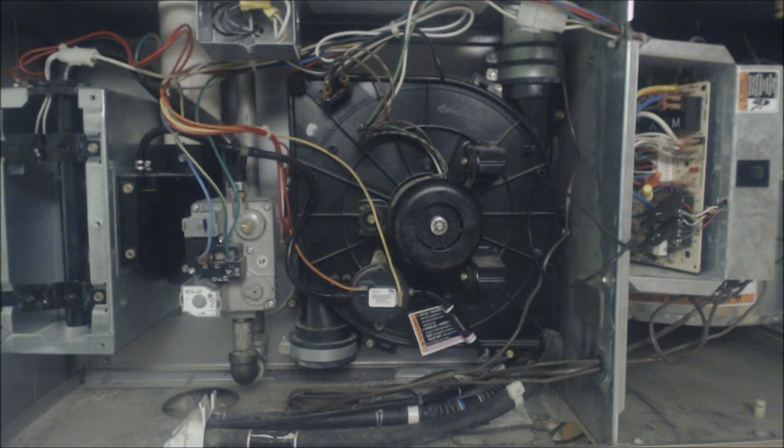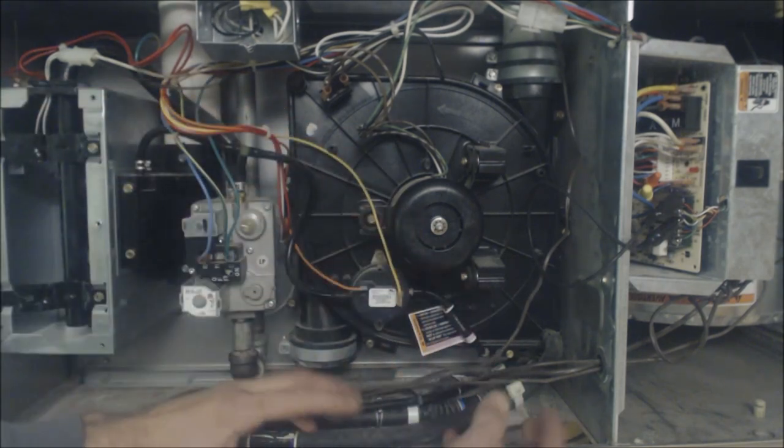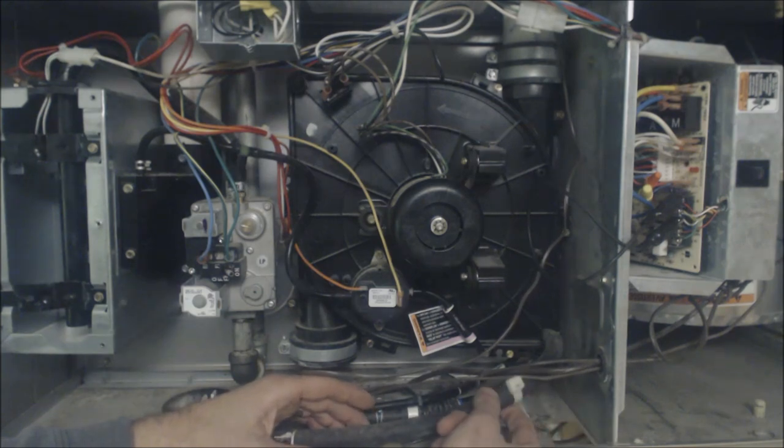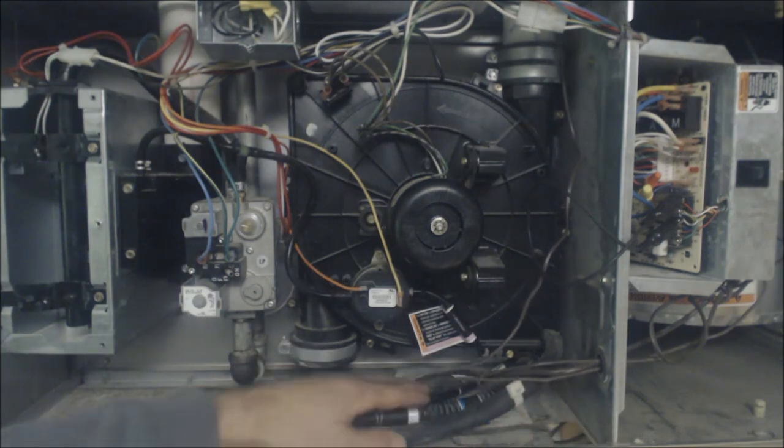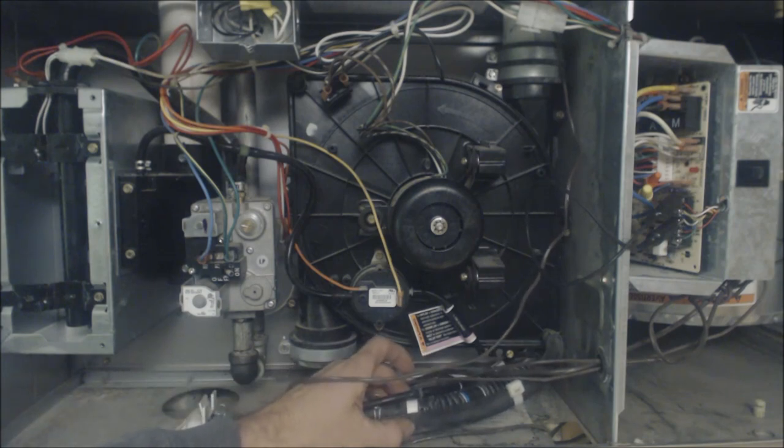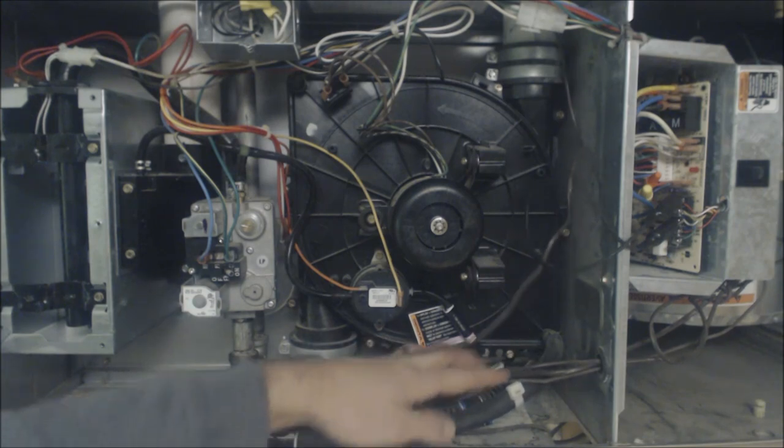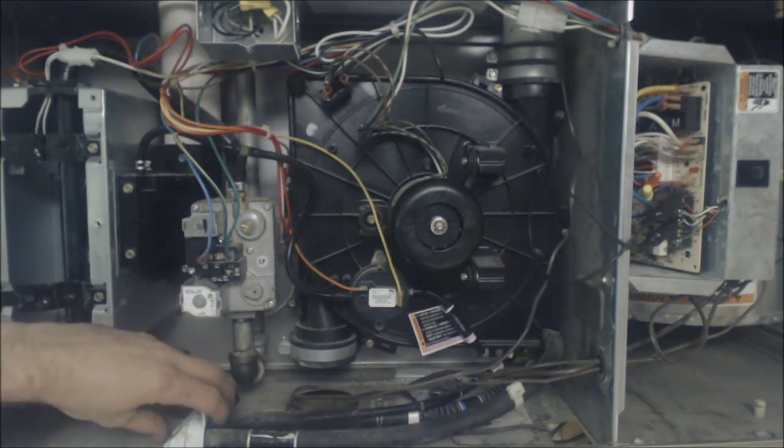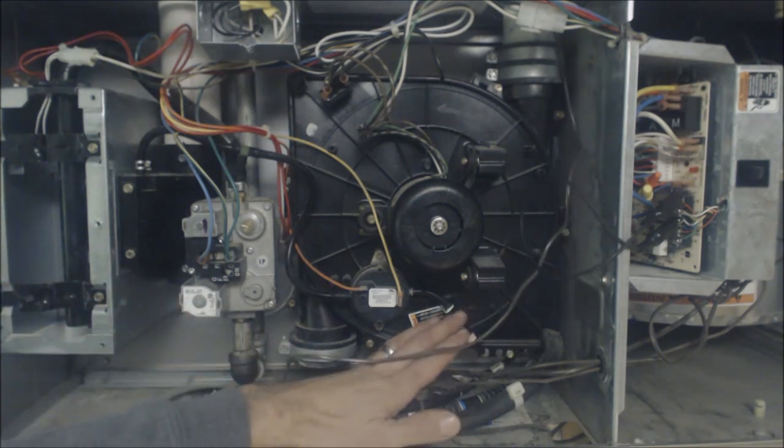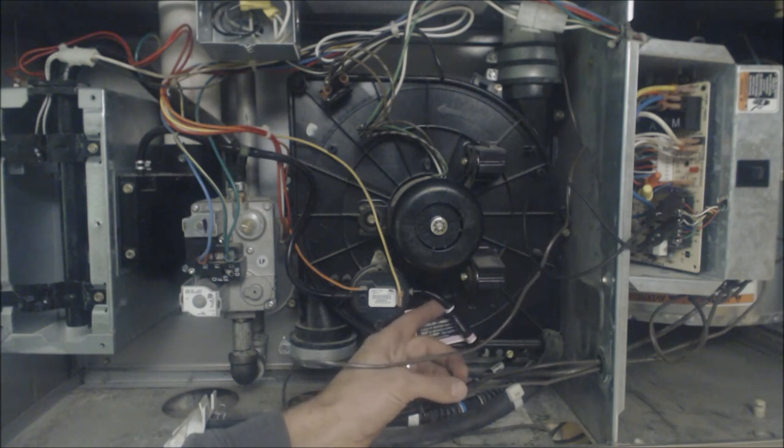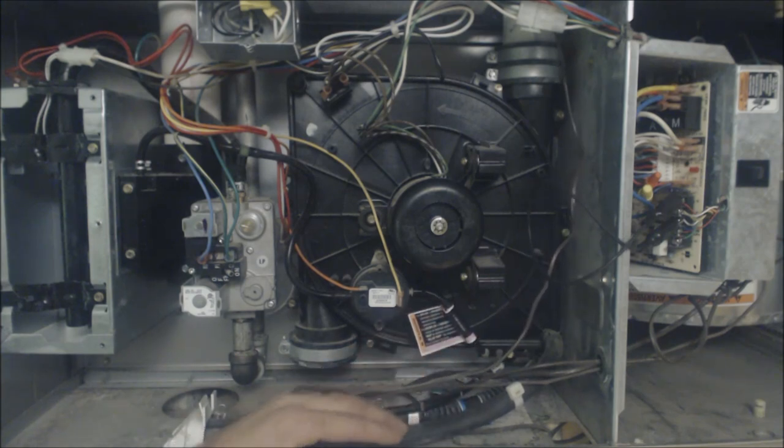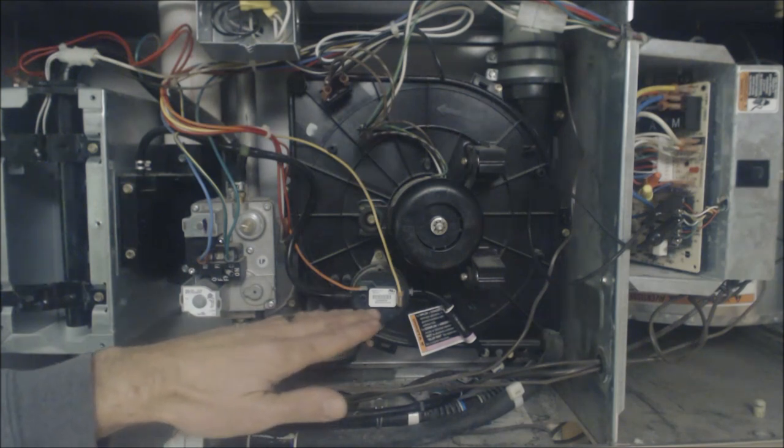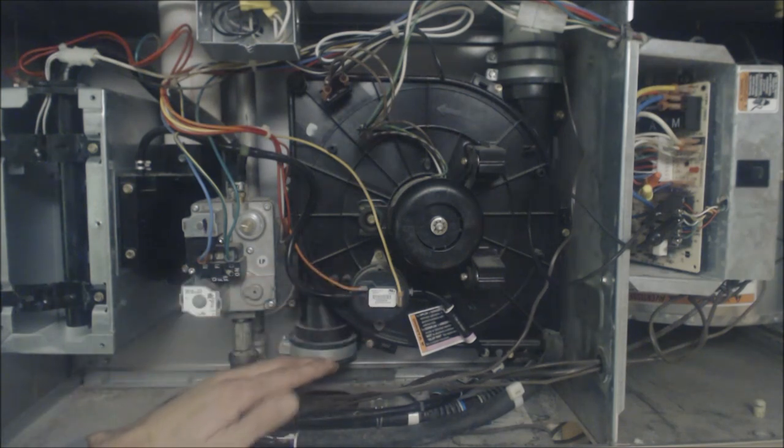So you can use that trick if you find that these are kinked. But anyway, if you have the water coming to the condensate trap and it's just backing up, backing up, backing up, then this pressure switch will not read properly, okay, and especially on the newer furnaces. But this right here is not normally the problem.